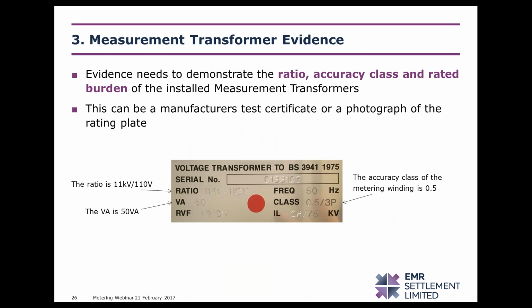The next area that has caused issues has been evidence of the installed measurement transformers. The metering statement requires you to demonstrate what ratio, accuracy class, and rated burden of any installed measurement transformers connected to the CMU meters are. This can be both current transformers and voltage transformers. The easiest way to do this is through a manufacturer's test certificate for the measurement transformer, or one of the allowed options is a photograph of the rating plate.